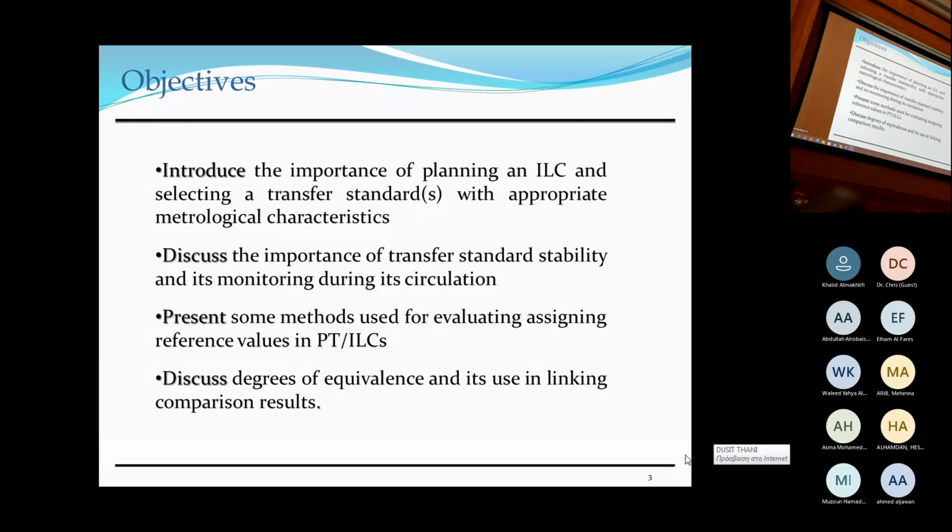Transfer standard so that it's capable of validating the CMCs of the laboratory participating in the PT. So it's very, very important that the selection be made correctly of the transfer standard. Otherwise, it's just futile to do an exercise of this sort, because if it doesn't have the right amount of metrological characteristics, it's just going to blur the picture and you won't be able to see almost anything.